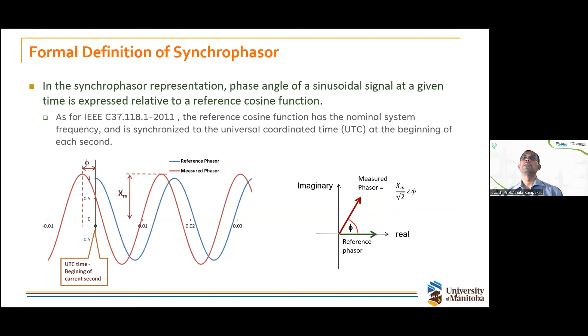And so if you start observing synchrophasor measurements from a signal which has a frequency not equal to the nominal frequency, it will appear as having a changing phase angle. For example, the deviation is constant in this case. So if you are reporting at, let's say, 12 measurements per second, in 1 second you will see 12 measurements coming. At each measurement, the phase of the signal will be shifted by 30 degrees. So after 12 measurements, it will again come back to the 0 phase shift.